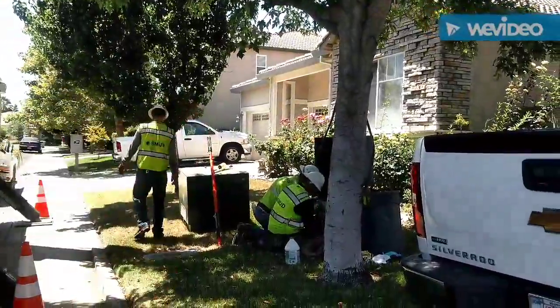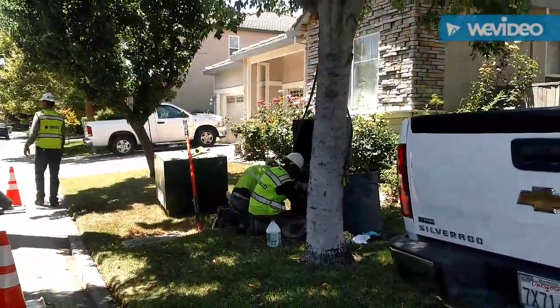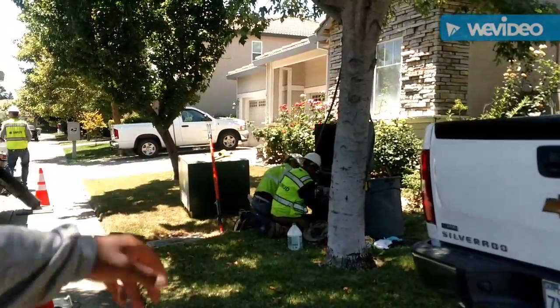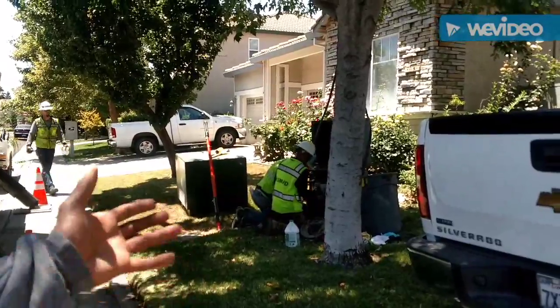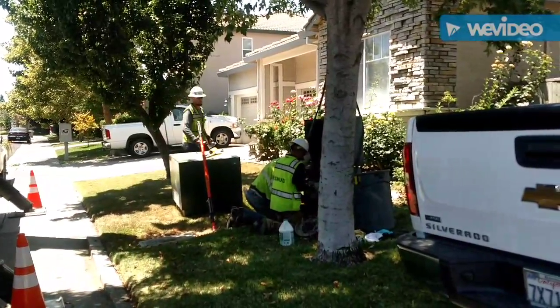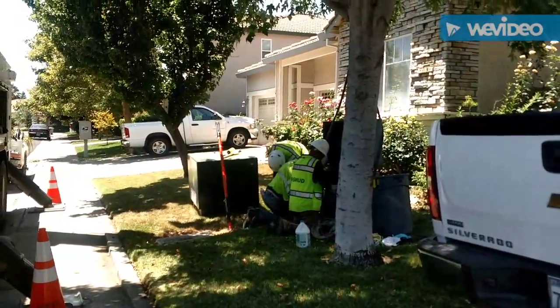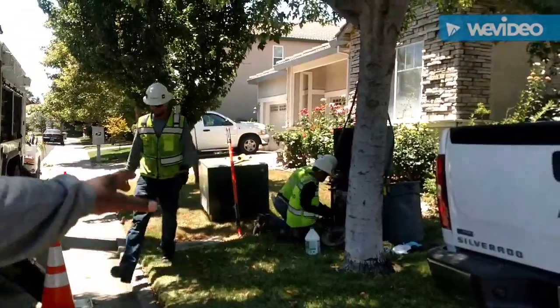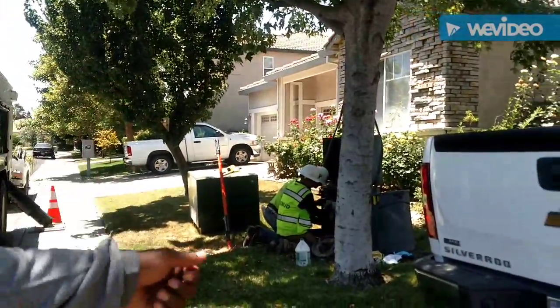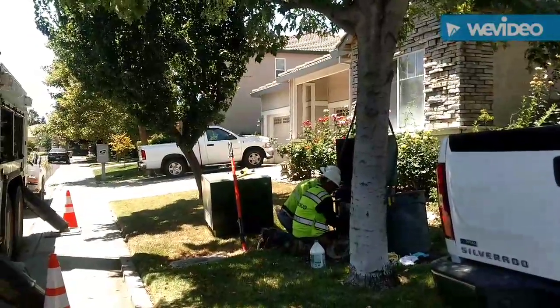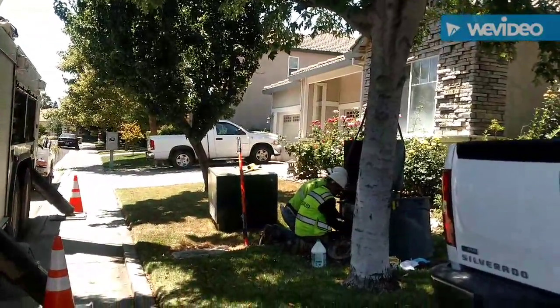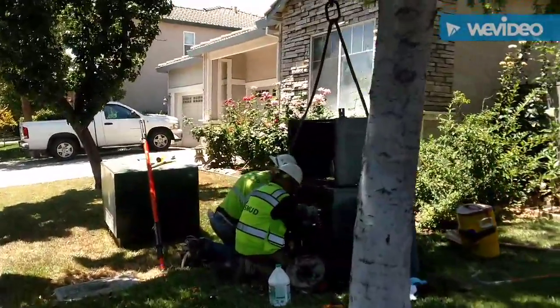And this is Keno Grigsby. He's the foreman on this job out here in Elk Grove. Keno, tell me a little bit about what you're doing out here on this site. This transformer's rusted and it was leaking, and when that happens, a failure can happen when temperatures go up or the oil pressure gets low. So we're out here doing it now. We've notified the customers, that way we can have a short outage, because if it went out on its own, then it'd be out for a couple of hours. It'd take longer. So we're just trying to prevent that issue from happening. Plus, when our guys come to do switching, they want to open the transformer and not have something fall on them while they're doing that. So, all right, maybe we can take a look and you can tell me a little more about what they're up to here now.